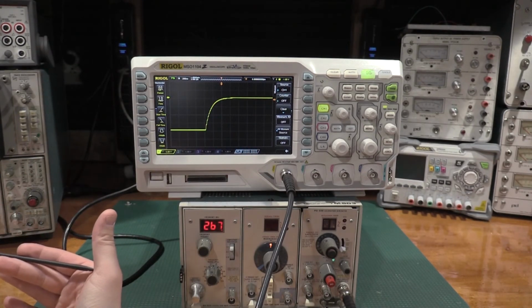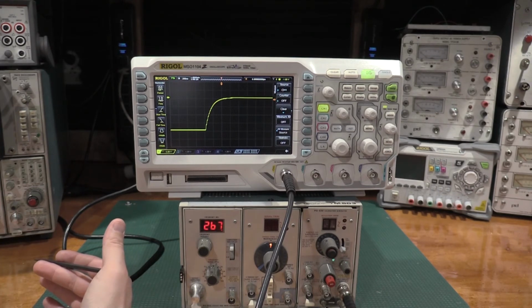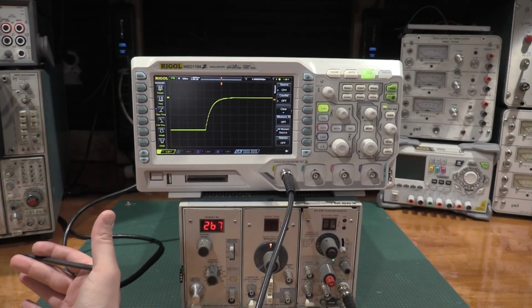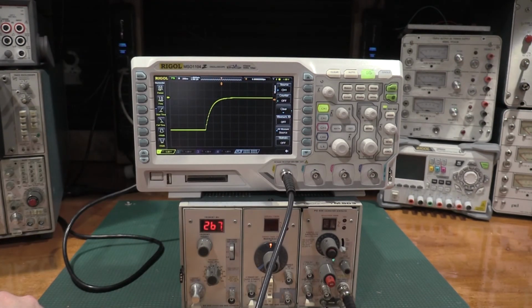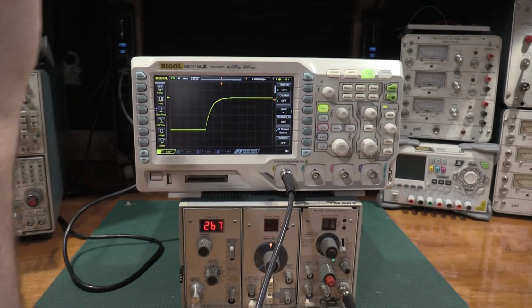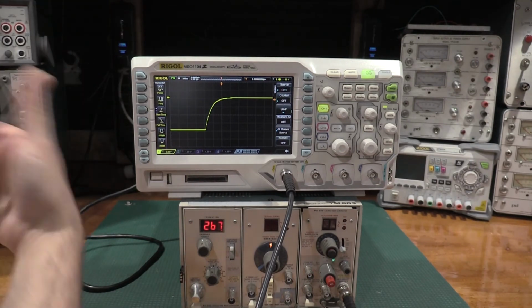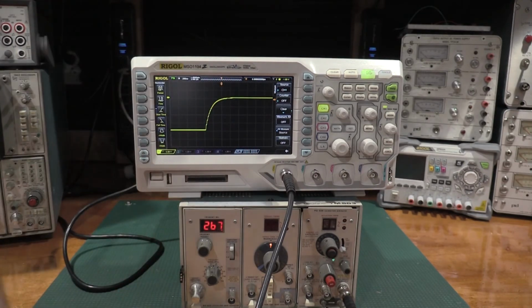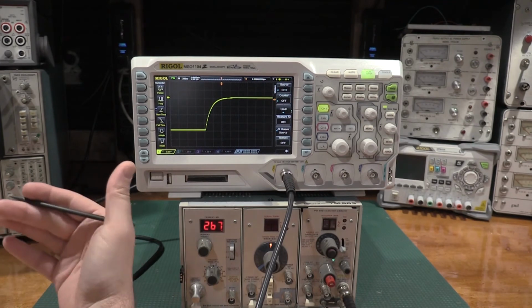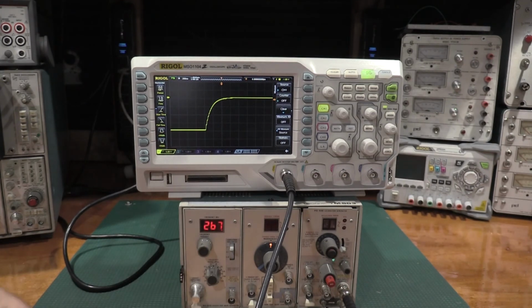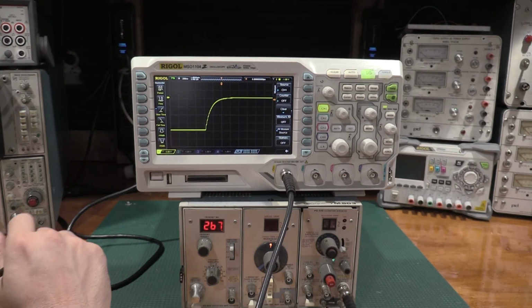Any good square wave generator can do that as long as it doesn't have a ton of ringing and overshoot. So is that critically important? Not really. The Type 106 is just a square wave generator that's very variable. Any good square wave generator can do that, especially when you're tuning the amplifiers, adjusting them and dialing them in. As long as you know that the square wave is clean, that's the important part. It comes up, stops, doesn't overshoot, doesn't undershoot, because that's what we're tuning out of the verticals.